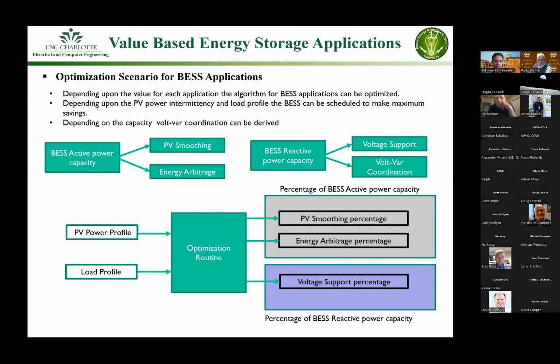You can have a 1 MVA capacity for an inverter, where you have additional cushion or room to have extra reactive power coming out from the inverter. Now, as you may know, the reactive power support from the inverter is different from the conventional way of supporting reactive power in the utility through capacitor support or voltage management directly from the regulator, because the reactive power coming out from the inverter is through the angular shift between the current and voltage, which happens inside the inverter. So it's a kind of free commodity which you can get from the inverter itself.